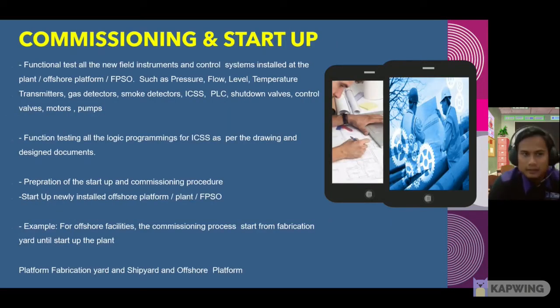And then for commissioning and startup, this is functional testing of all the new field instruments and control systems installed at the plant, offshore platform, or FPSO, such as pressure, flow, level, and temperature transmitters, gas detectors, smoke detectors, ICSS, PLC, shutdown valves, control valves, motors and pumps. Function testing also covers testing all the logic programming for ICSS as per the drawing and design document, preparing the startup and commissioning procedure, and then starting up the newly installed offshore platform, plant, or FPSO.